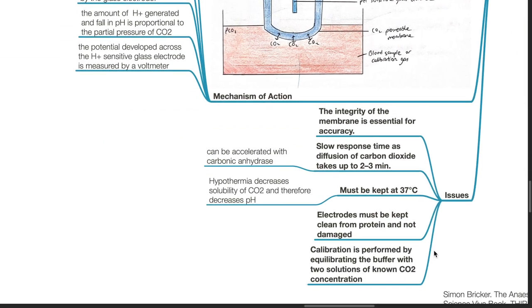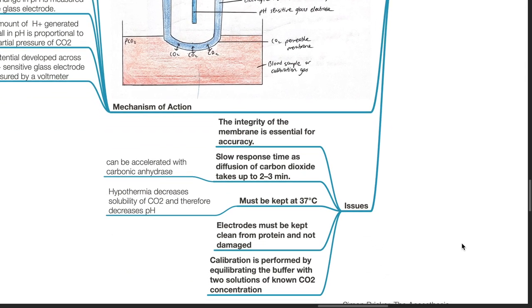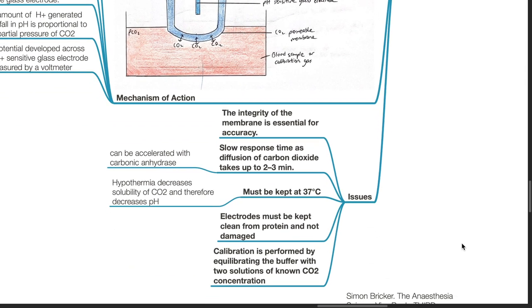The integrity of the membrane is essential for accuracy. Slow response time, as diffusion of carbon dioxide takes up to 2 to 3 minutes, though this can be accelerated with carbonic anhydrase. The electrode must be kept at 37 degrees Celsius. Hypothermia decreases the solubility of carbon dioxide and therefore decreases the pH. Electrodes must be kept clean from protein and not damaged. Calibration is performed by equilibrating the buffer with two solutions of known carbon dioxide concentration.